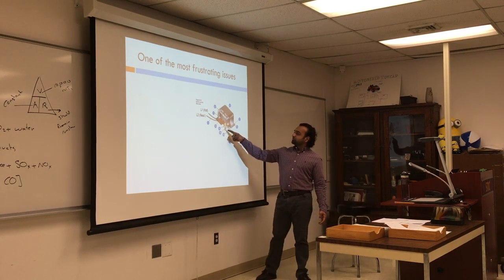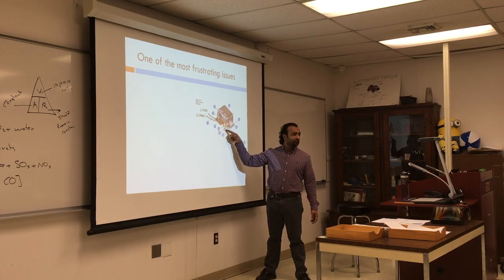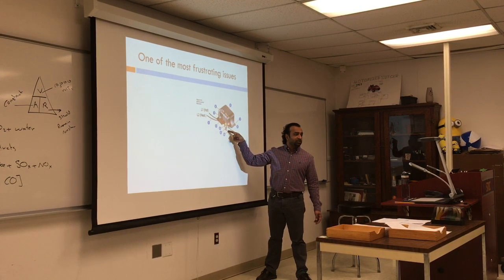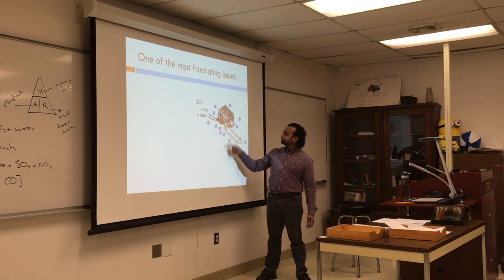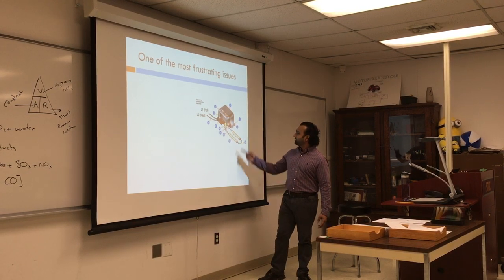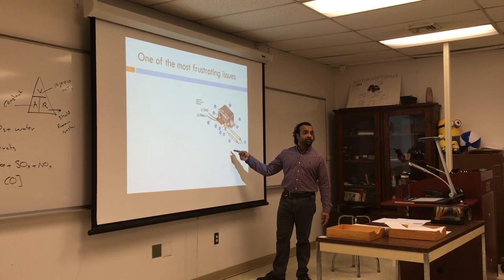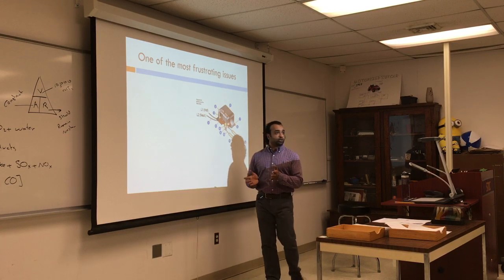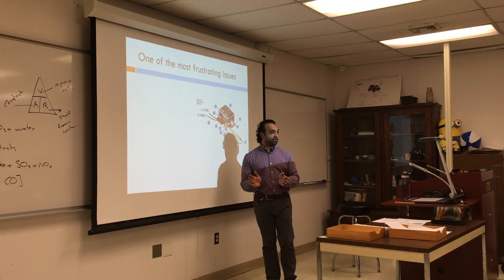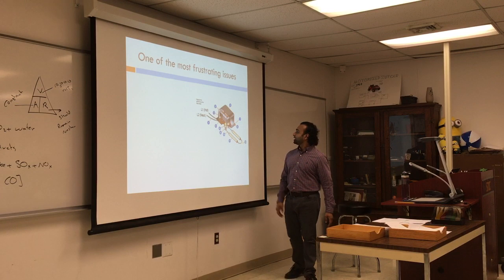Sometimes these bus bars do not touch very well, they touch but barely, or they can move, so make sure they're touching in a good way. What else could happen? These could crack, they could change. Again, sometimes you put back the electrodes and they are a little bit too far, or they're touching the plate, so that could be another issue.